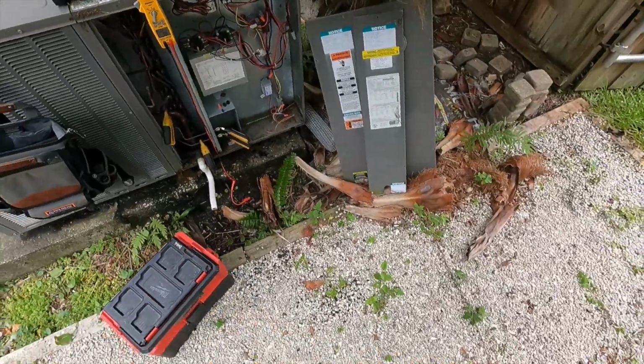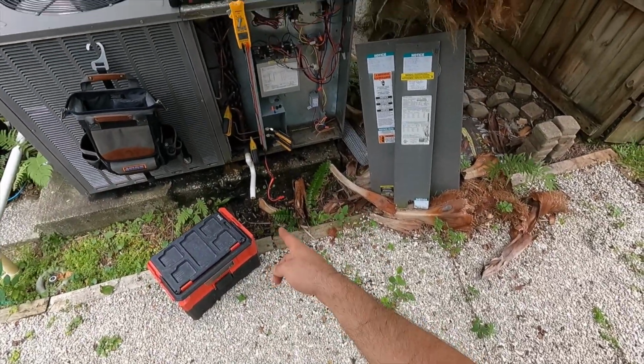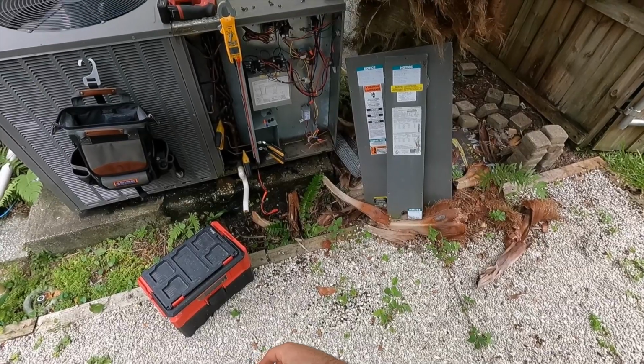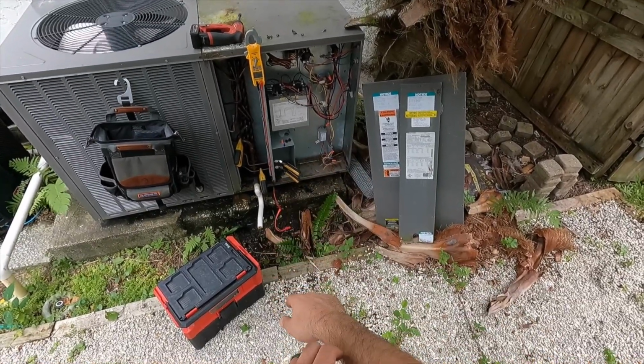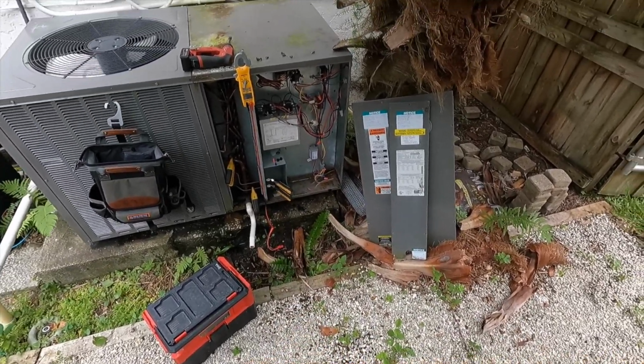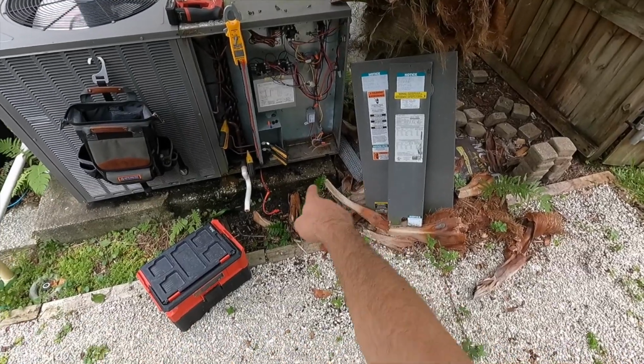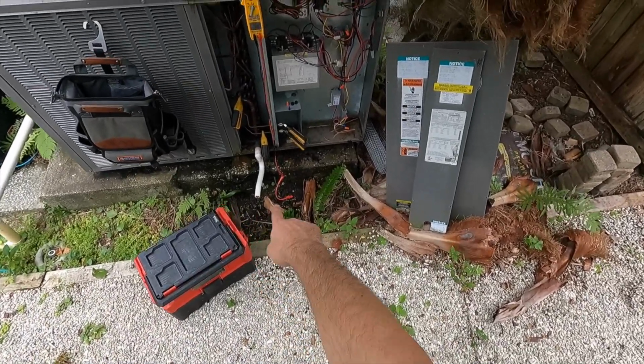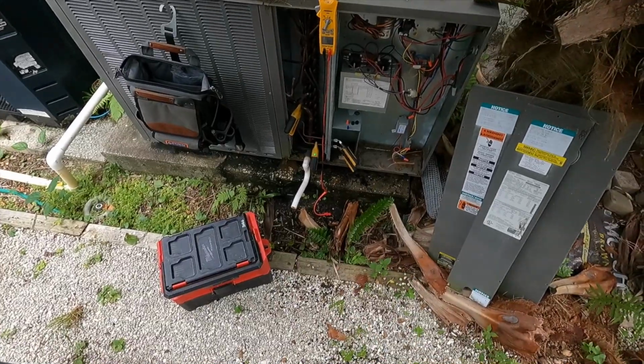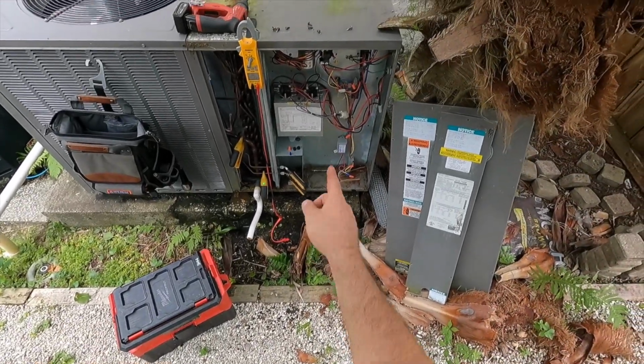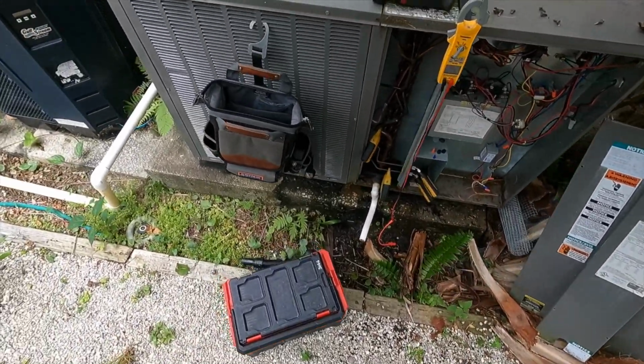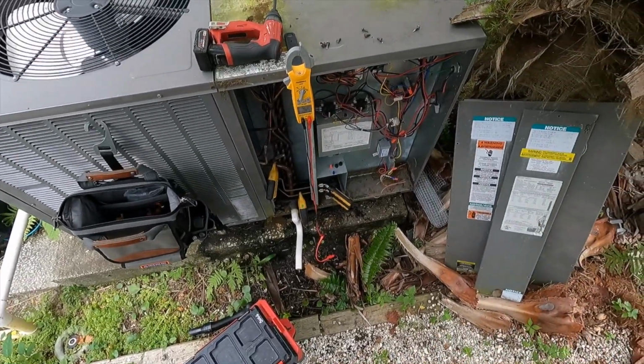I'm gonna go ahead and work on getting that pan out, the top of the unit here off, so I can access the evaporator coil for disinfection and just check everything out, including the blower, and see what the bottom of that system looks like. With water all the way over here and that drain having been clogged, I can bet that whole bottom cabinet is filled with water and slime. So let's take a look.